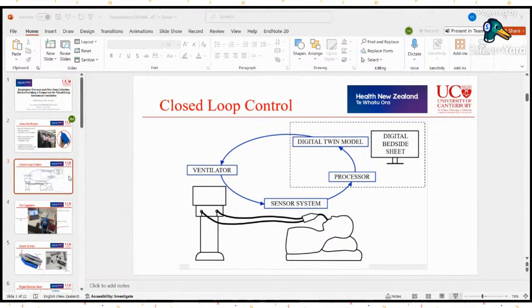Cool. So this is effectively what we mean by closed loop control. The ventilator is connected to the patient and supplying air support. Then we have our sensor system in series with this connection, and that's measuring pressure data. That data is sent to a digital bedside sheet, where the data is converted to flow and integrated with a digital twin model. The digital twin model is a mathematical model that will analyze the patient data, and based on a parameter that we are looking at reducing or optimizing, it can then find the best ventilator setting. The best ventilator setting decided from the digital twin model is then sent back to the ventilator, and it'll update automatically and can fully automate the care.